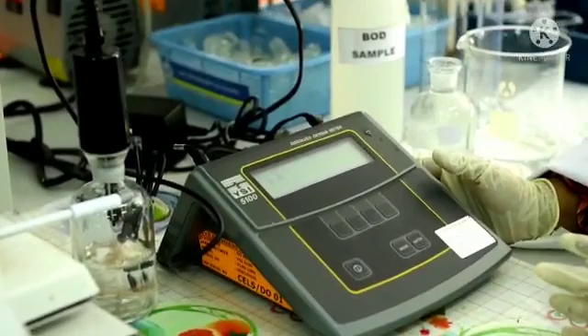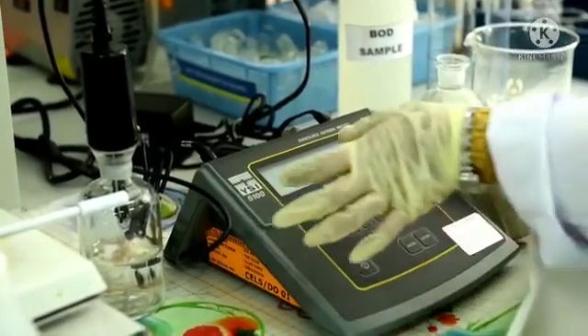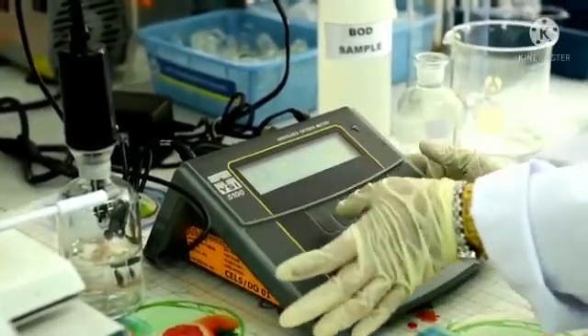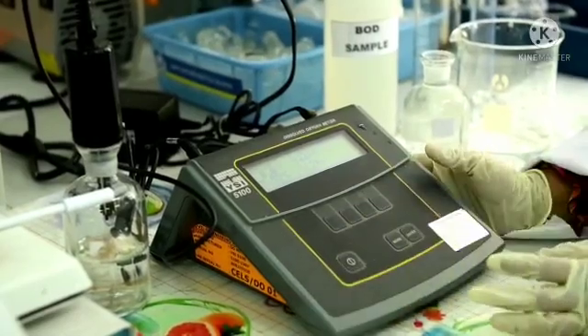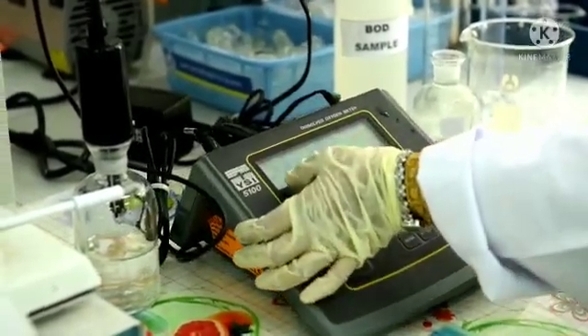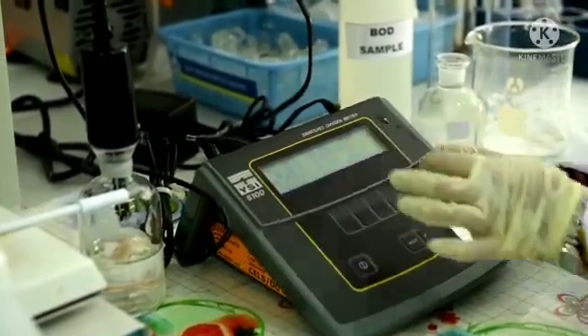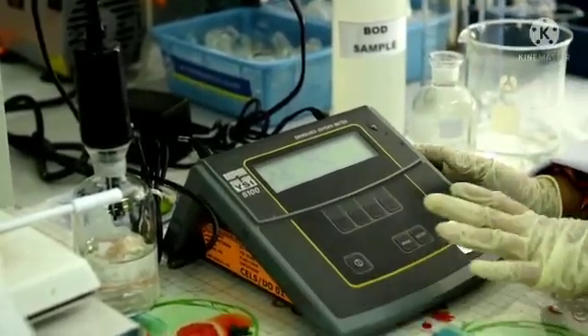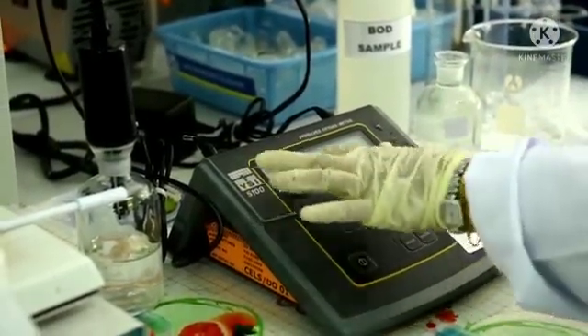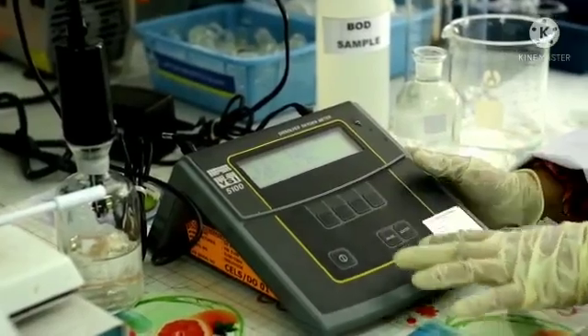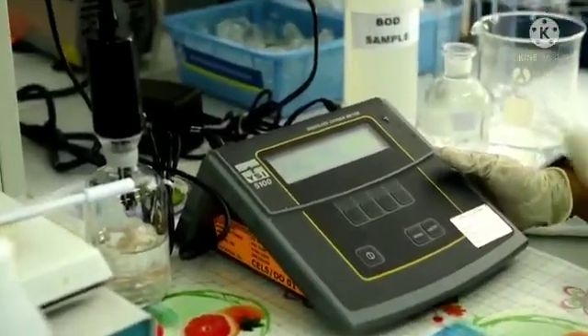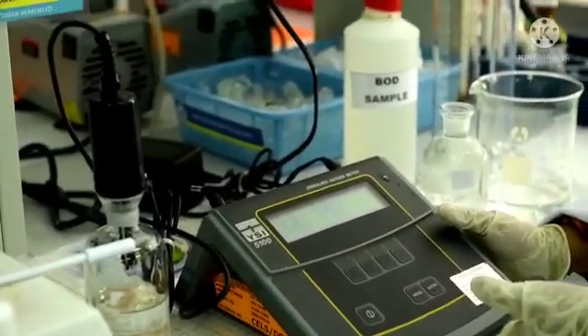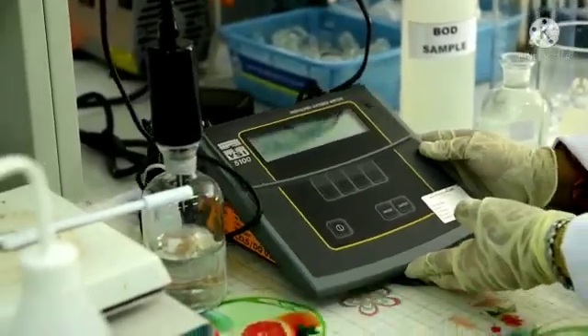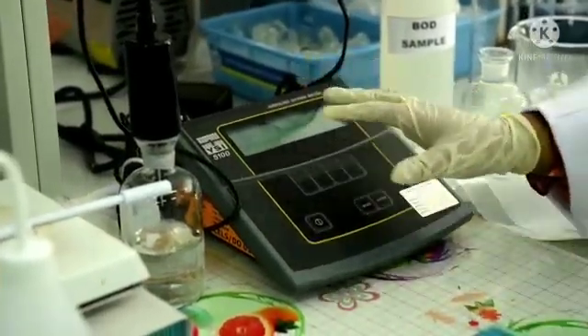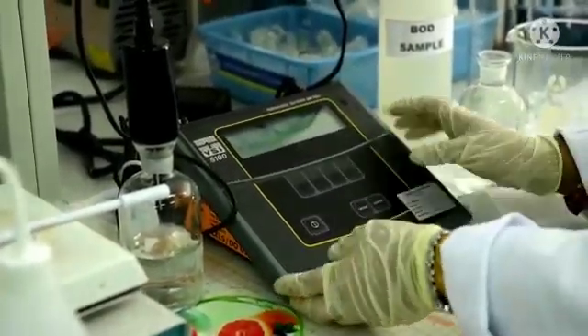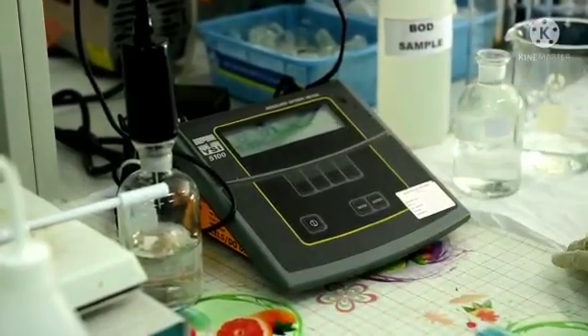Wait, and then press auto cal also. You will see here DO calibration saved. That means the equipment now is stable. But if you see unstable, you must wait and press calibrate and auto cal again. And then you press mode to go to the main page. Now we can use this equipment.